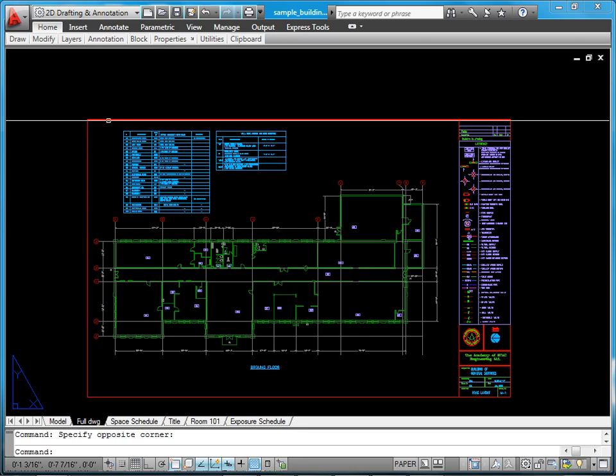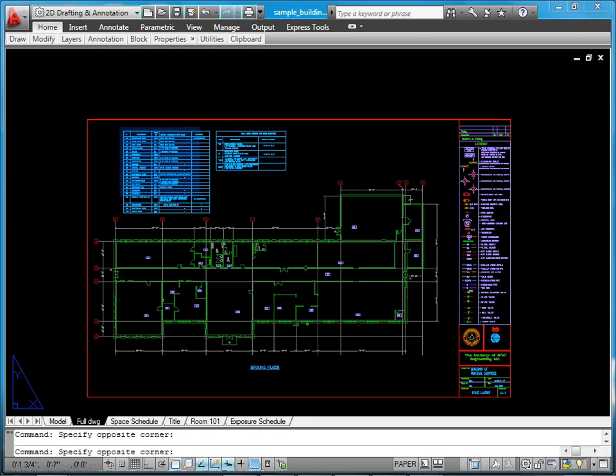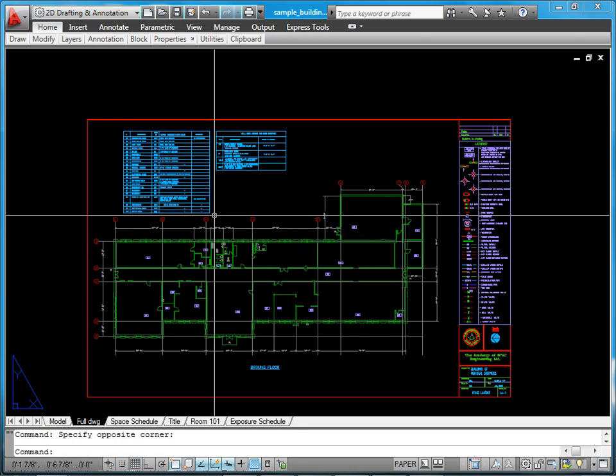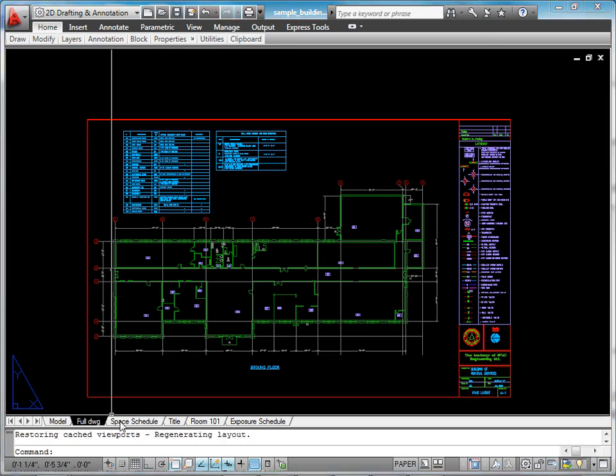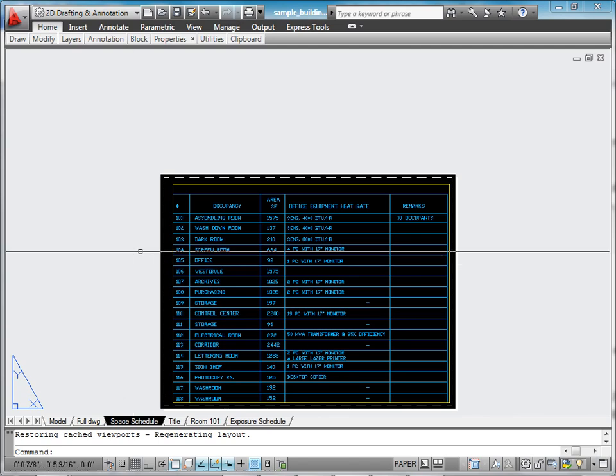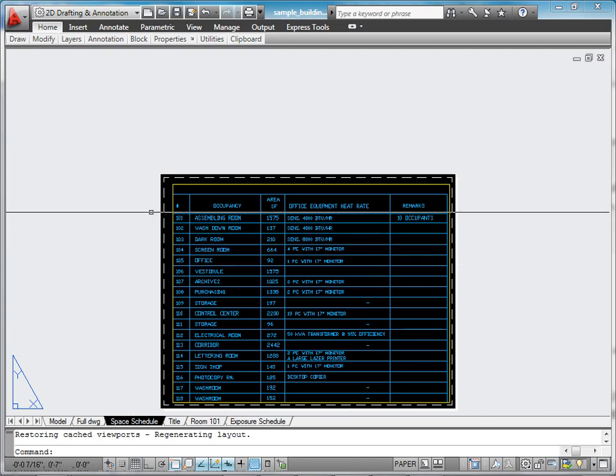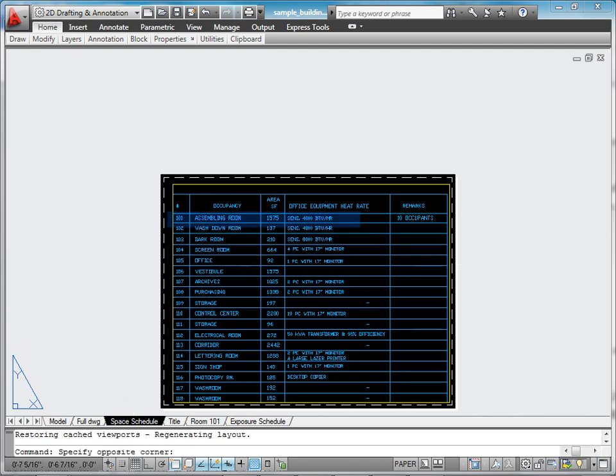The space schedule at the upper part of the drawing specifies the occupancy type, floor area, and equipment heat gain rates for each space in the building. For example, the schedule shows that assembling room 101 has a floor area of 1,575 square feet, is designed for 10 occupants, and houses equipment with a heat gain rate of 4,000 British thermal units per hour.